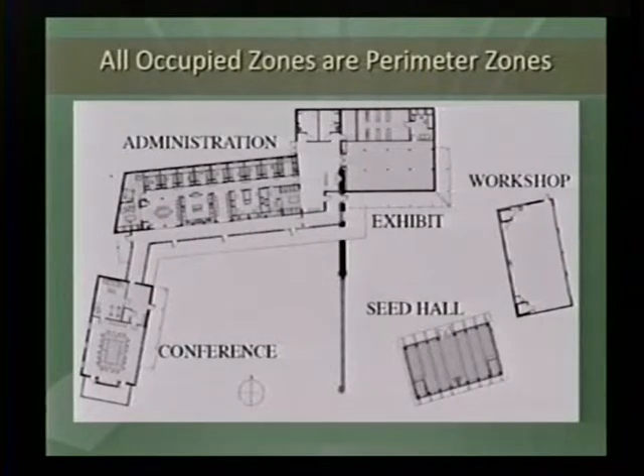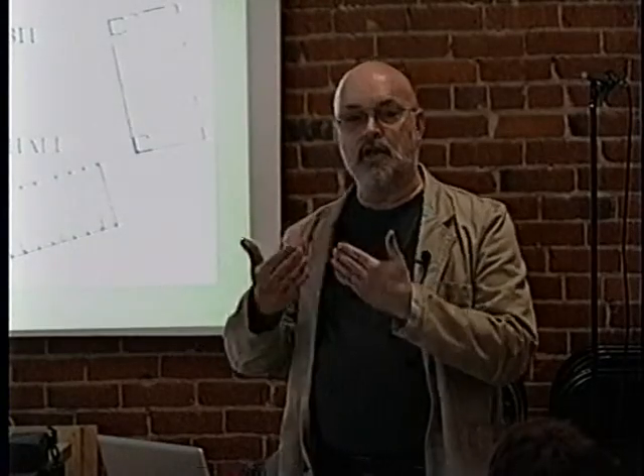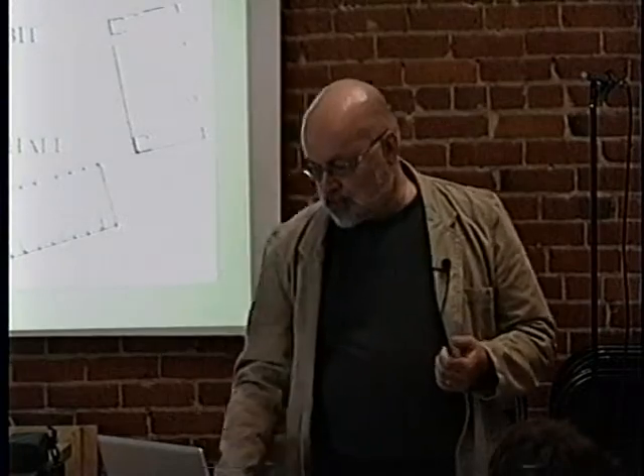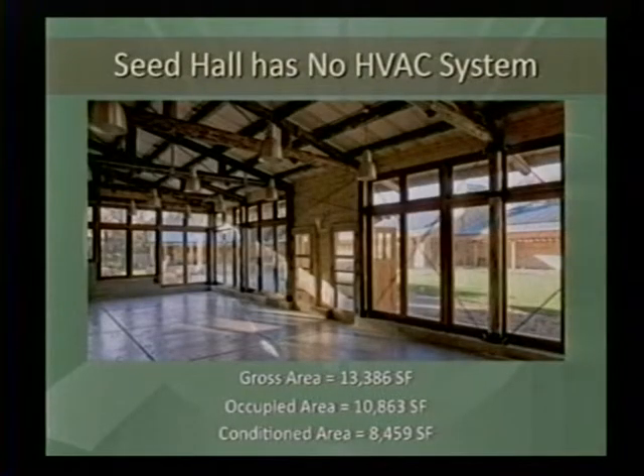We won't use it more than once a week. So in the winter, let the mechanical system just heat it to 55 degrees. We'll bring it up to temperature with a wood heating stove whenever we occupy it. And they wanted that conference wing on a wood floor rather than a slab on grade. So that has a slightly different system. There's actually fin tube convectors rather than radiant slabs in that system. But again, thinking about the program, thinking about the uses, and looking at how you adjust systems relative to those uses. This is the interior of the seed hall without the HVAC system.